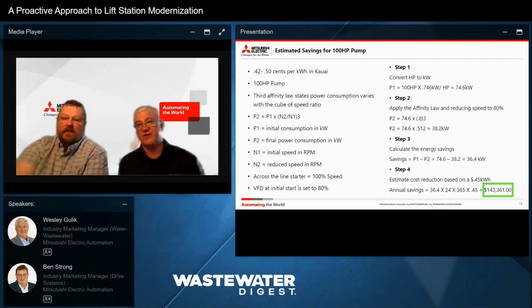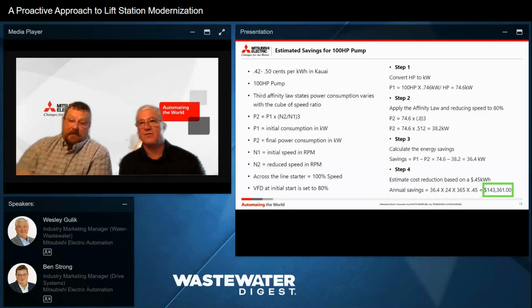Correct. Yeah. So, a quick feedback point: with that return, in Hawaii, they made a decision within a week. It's a no-brainer, because the return on investment, we're talking months, not years. We're talking within 4 or 5 months. So definitely something that they went from soft starts to variable frequency drives to take advantage of the cost savings. Yeah, you do have to do the engineering on this. You have to ensure that your system can take a lower flow rate and a lower frequency and still do what you need to do. But here's an option for you to save money.